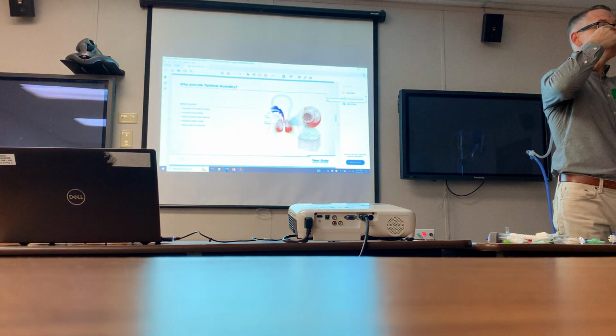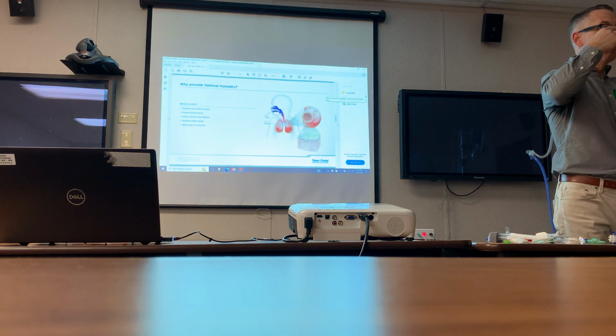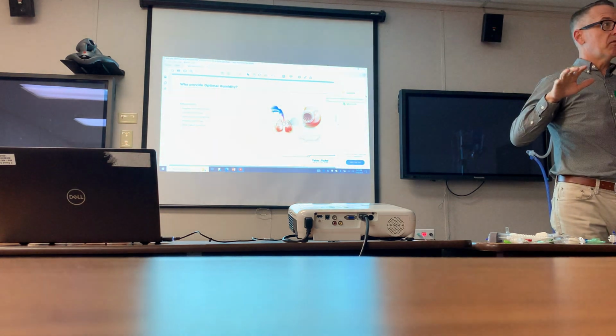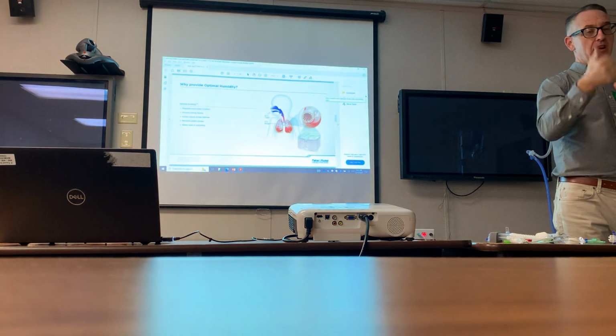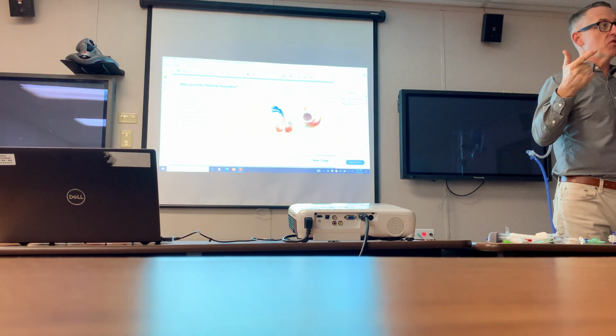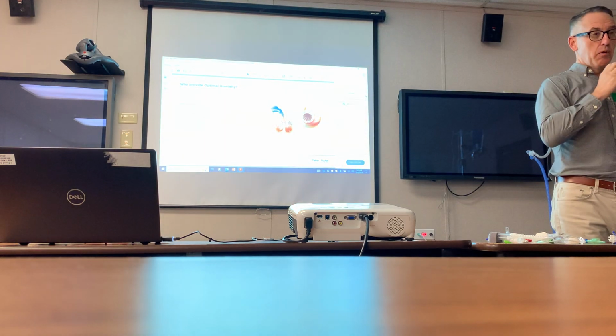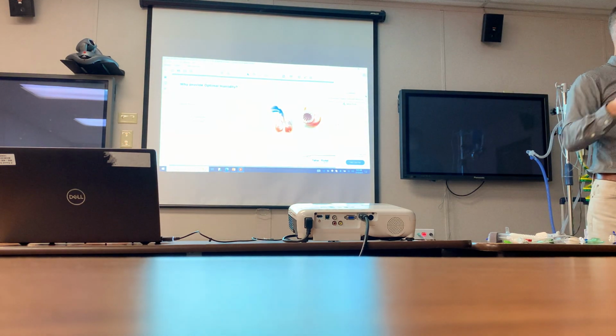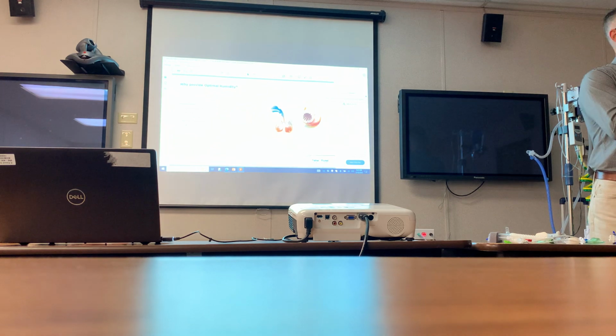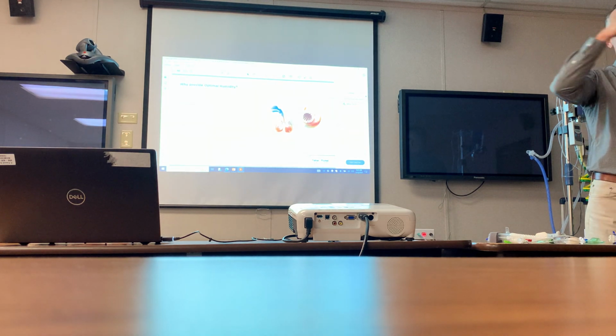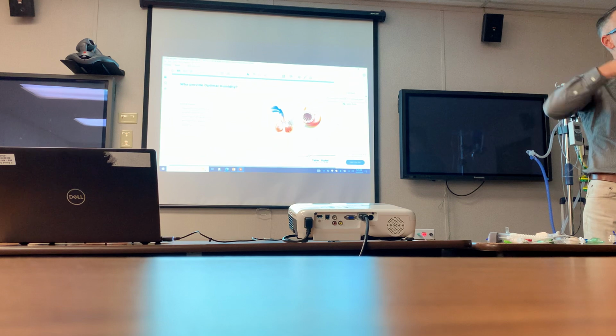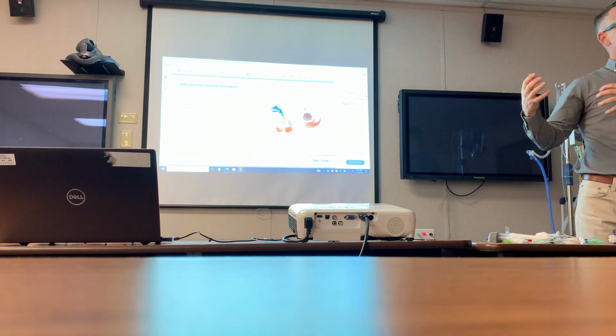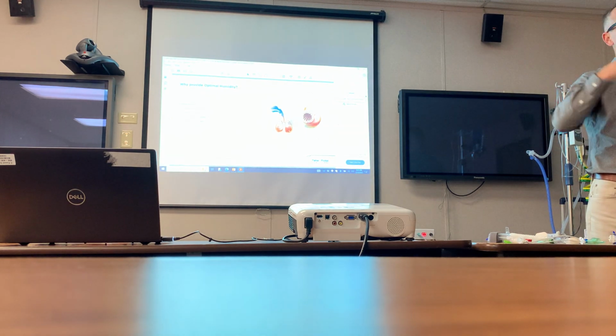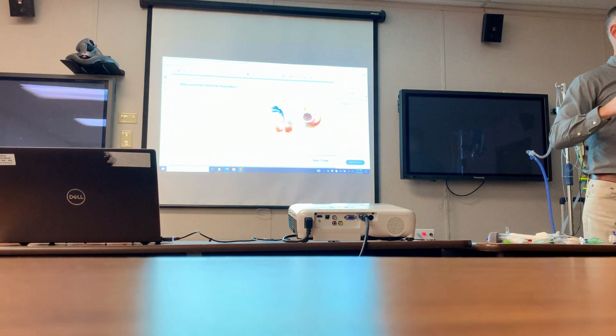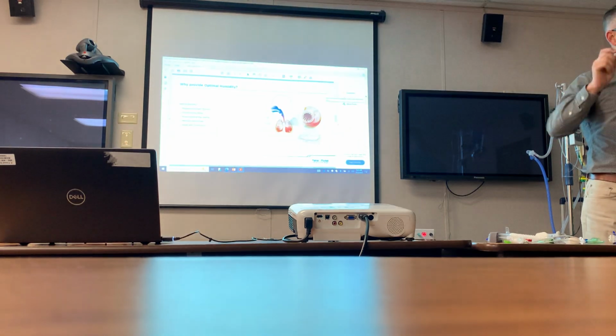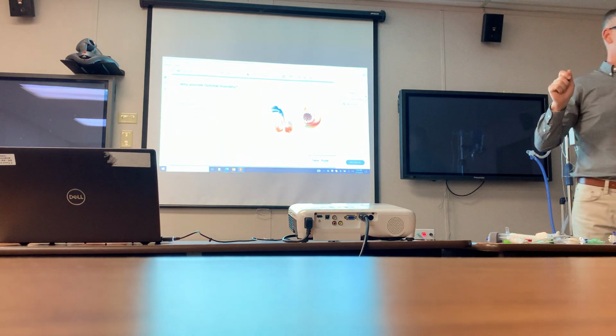Even though it starts to moisturize, in a baby or a NICU setting, they don't have the spare energy or the spare moisture to be able to heat up air. If they were in utero, all that temperature and moisture is already provided for them by the mother. So when they come out premature, they don't have that excess heat and humidification themselves to heat up that air. In an adult setting, we've got a lot of spare capacity, so you can play with it a little bit more when they complain about it, but you still would like to get them up to 37 as well.